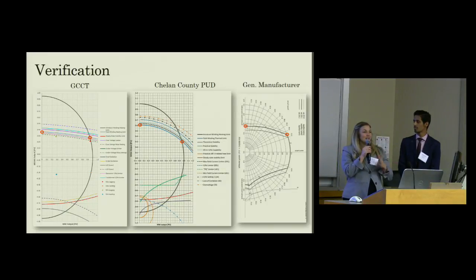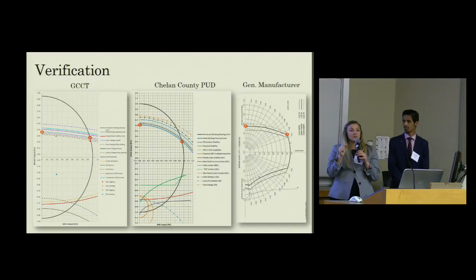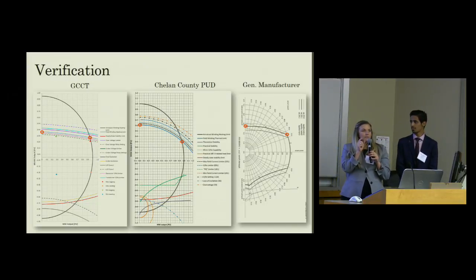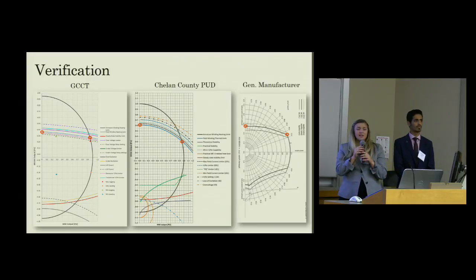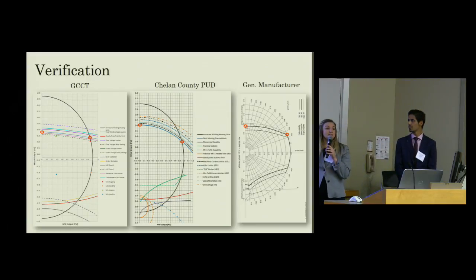We were aiming for 5% accuracy. Like I mentioned, with the field winding heating limit and the armature winding heating limit, their intersection should be at the machine's rated power factor, so we had very little change there. But what was different was our reactive power axis, and that's what I was talking about with theoretical versus practical. We did similarly for the steady state stability limit.